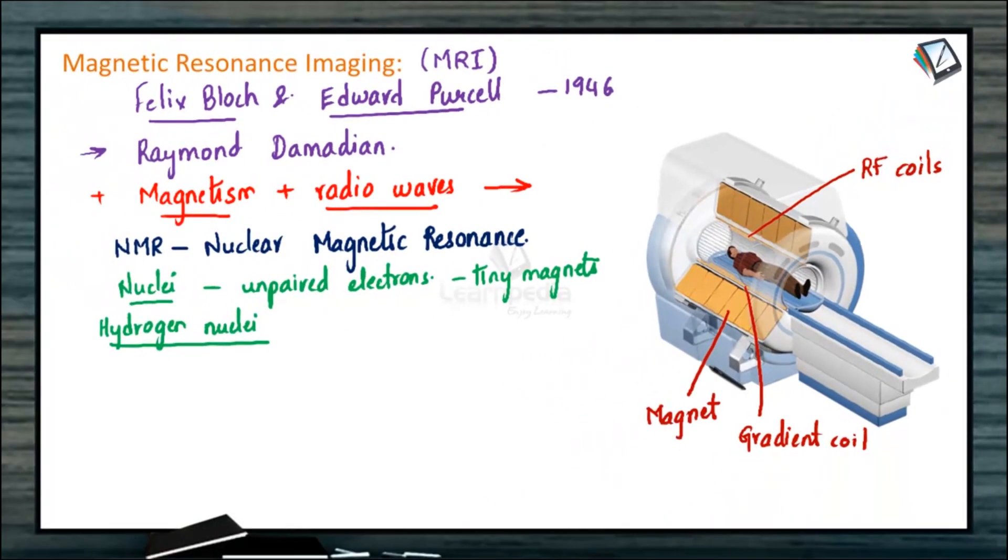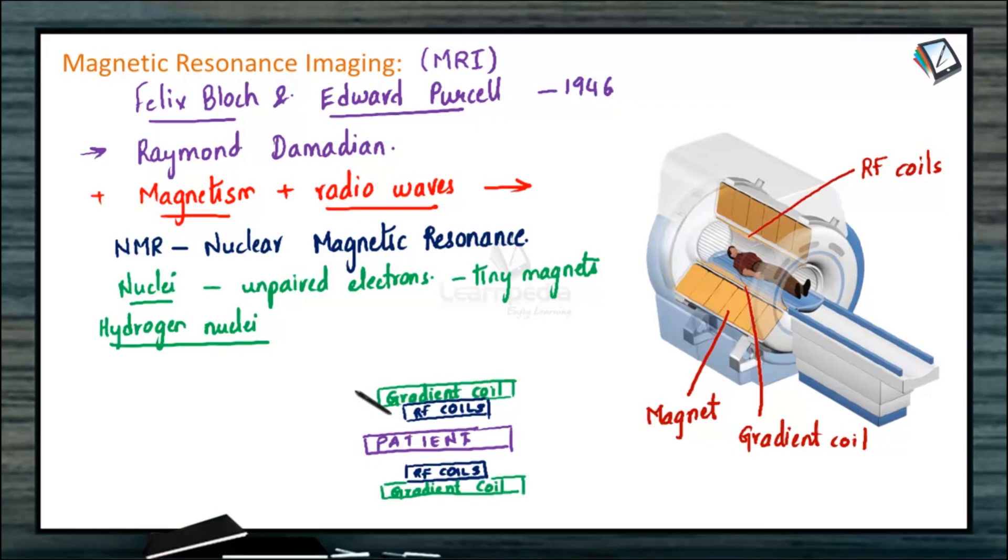Now outer to this RF coil is the gradient coils. So this thin line, if you can observe, this is the gradient coil. And finally, surrounded by the primary magnet. So all these coils as well as the magnet are present on 360 degrees. On all sides it is present. Now suppose if the patient is lying here, surrounding the patient you have the RF coil and surrounding this RF coil is the gradient coil. And surrounding this gradient coil is the primary magnetic field.